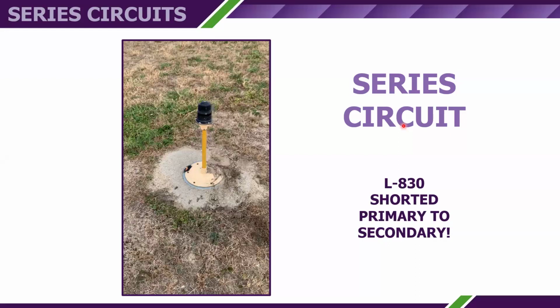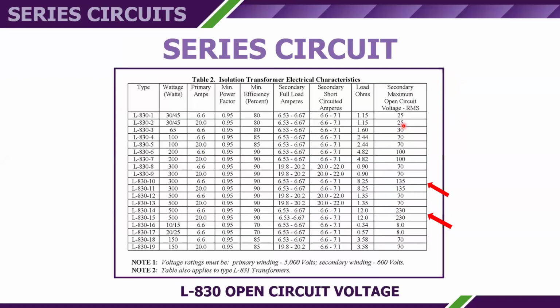If you pick up the light, you become part of the path for current to flow. Open circuit voltage is up to 230 volts. You get 230 volts open circuit on a 500 watt L830 isolation transformer. That's going to be normal open circuit voltage. On a 300 watt isolation transformer, normal open circuit voltage is 135 volts.